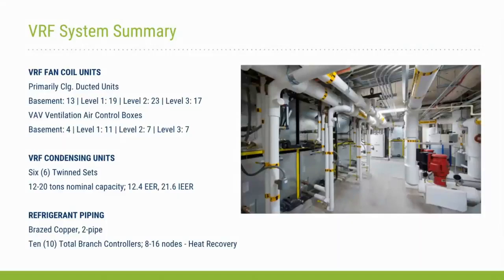On the indoor fan coil unit side, we primarily used ducted low-profile ceiling-mounted units. These were installed with relatively short amounts of supply ductwork and provided with ventilation air from a separate rooftop-mounted dedicated outside air system. That dedicated outside air system did have additional zone-level control with the VAV single duct boxes in the quantities that you see on the screen. Refrigerant piping was brazed copper in a 2-pipe configuration with 10 branch controllers, each with 8 to 16 nodes.